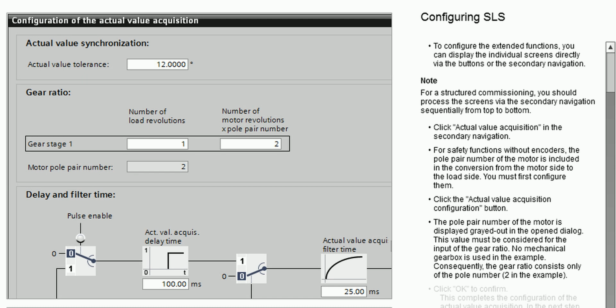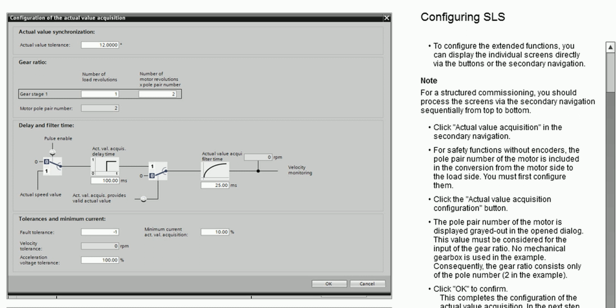The pole pair number of the motor is displayed grayed out in the open dialog. This value must be considered for the input of the gear ratio. No mechanical gearbox is used in the example. Consequently, the gear ratio consists only of the pole number, 2 in the example. Click OK to confirm. This completes the configuration of the actual value acquisition. In the next step, configure the safety function.